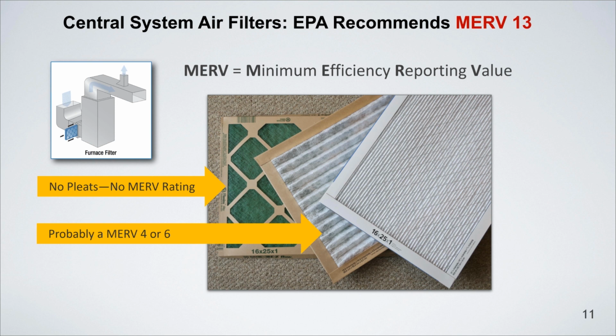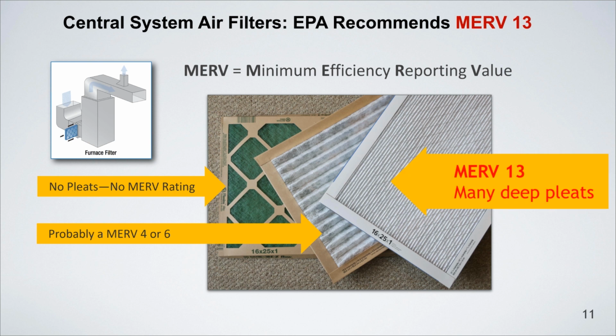Those are pleats in the filter to allow more surface area in the same face area, and that way you can slow the air down a little bit, and you can put it through paper, which is a better filtration than just a polyester mesh, and you're going to trap more of those particles. But at MERV 4 or MERV 6, you're going to get the larger particles. And as Terry pointed out in the earlier discussion, there's nothing wrong with taking big particles out of the air. That's a good thing to do too, but it doesn't address the small particles. For that, you need something like a MERV 13.